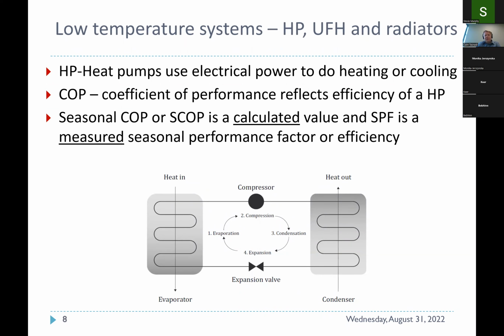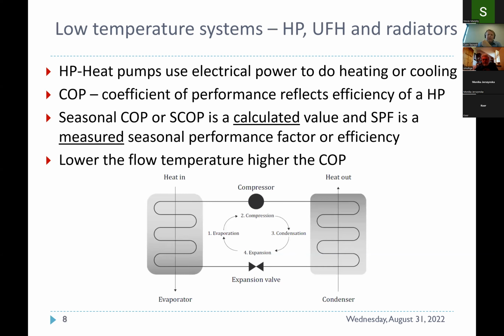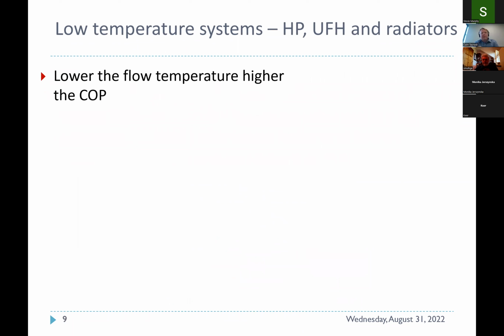Seasonal COP, or SCOP, is a calculated value, so all these are kind of lab tested values. And an SPF, or seasonal performance factor, is a measured value. So you will find that typically, depending on the way you operate a system, there is a variation between an SCOP and an SPF, because SPF is the actual real data, what has happened there. Ideally, and what I want people to always remember is that the lower the flow temperature, the higher the COP, or the efficiency. Again, lower the flow temperature, higher the COP.